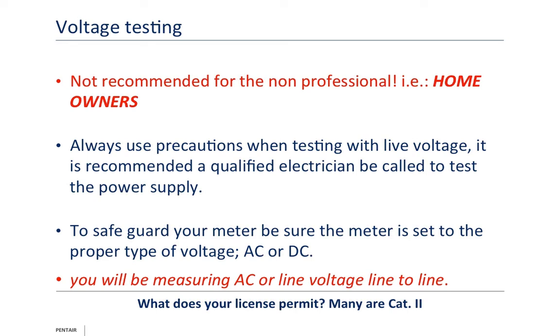Voltage testing, don't let the homeowner do it. I just don't recommend it at all. I also fully respect that, as a well driller or a pump installer, you're nervous around it. Okay? But here's a few tips. One, get some alligator clips so you don't have to hold it. Two, always measure L1 to L2. Don't measure each leg to ground.